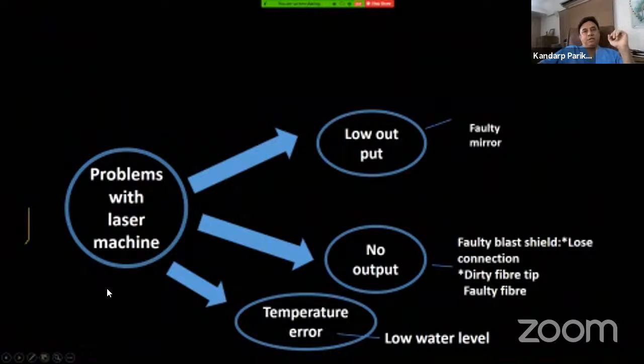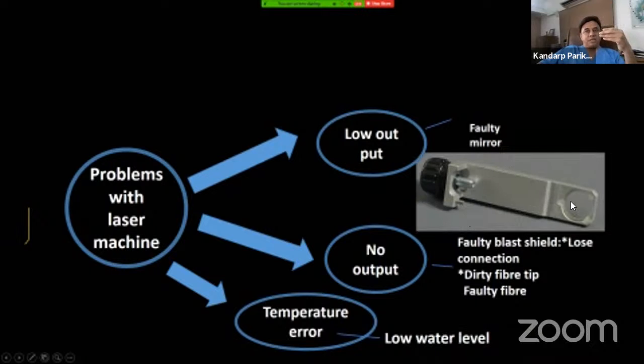Now you have initiated the laser machine. The machine does not start. What to do? There is no output. It means the blast shield is faulty. This is a blast shield, which is located in your machine between the laser outlet and a connector for the laser fiber. Whenever laser energy comes back to the laser machine because of a faulty fiber or dust over the fiber, it will damage the mirrors. In order to prevent the damage to the mirror, this glass shield is kept in between, a kind of shock absorber system. So the blast shield needs to be changed if you don't have any output.